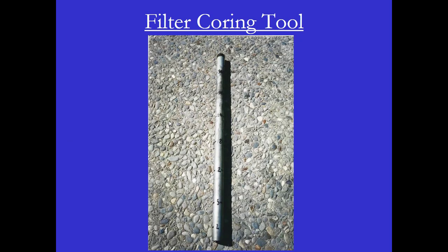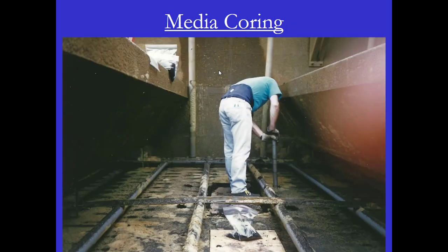Another important tool is the filter coring tool. I made mine with a one-and-a-half inch galvanized pipe, marked with a magic marker at two inch, six inch, 12 inch, 18 inch, 24 inch, 30 inch, and 36 inch. The media coring tool collects media from various locations in the filter at various depths, and that media is put into a bag to create a composite. That composite is sent to a laboratory to test for the uniformity coefficient and the effective size of the media to see if they're well matched.